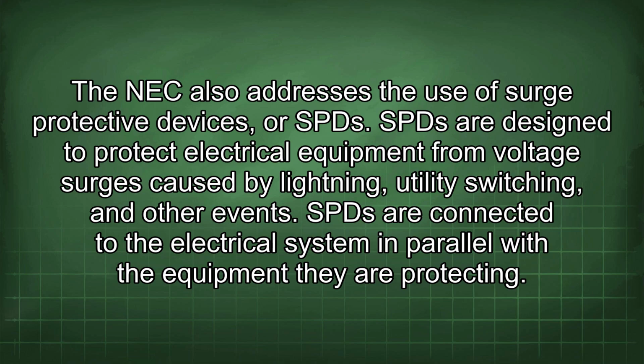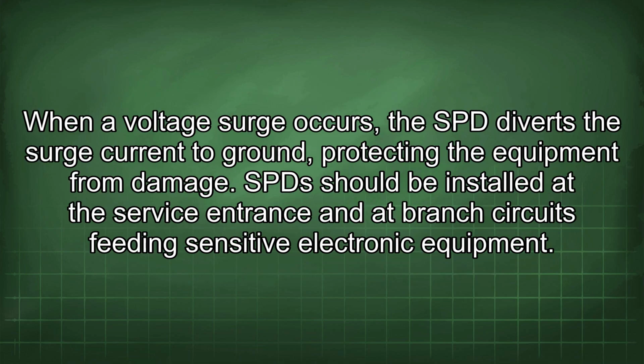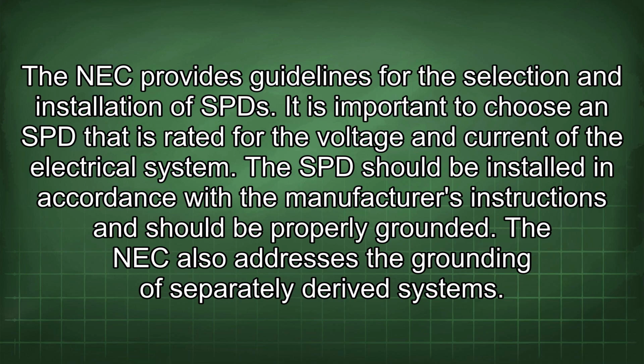The NEC also addresses the use of surge protective devices, or SPDs. SPDs are designed to protect electrical equipment from voltage surges caused by lightning, utility switching, and other events. SPDs are connected to the electrical system in parallel with the equipment they are protecting. When a voltage surge occurs, the SPD diverts the surge current to ground, protecting the equipment from damage. SPDs should be installed at the service entrance and at branch circuits feeding sensitive electronic equipment. The NEC provides guidelines for the selection and installation of SPDs. It is important to choose an SPD that is rated for the voltage and current of the electrical system. The SPD should be installed in accordance with the manufacturer's instructions and should be properly grounded.